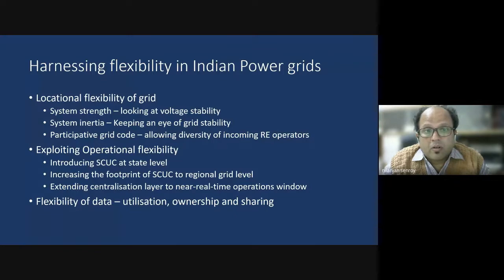Remember, local to state to national transition of the grid through interregional links, and tariff-related constrained transmission strategies may not always allow adequate inertia availability throughout the system. So you may have a lot of generation at one location, but the constraints in transmission do not allow this inertia to be available in other parts of the grid. Therefore, you need to distribute your synchronous machines throughout the grid.